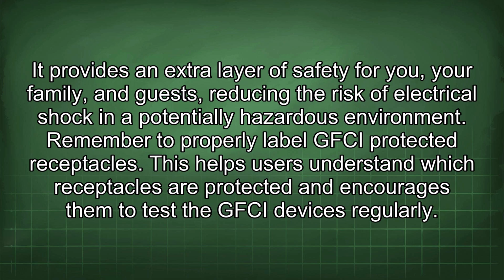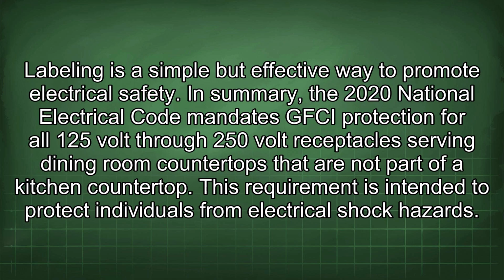a potentially hazardous environment. Remember to properly label GFCI protected receptacles. This helps users understand which receptacles are protected and encourages them to test the GFCI devices regularly. Labeling is a simple but effective way to promote electrical safety. In summary, the 2020 National Electrical Code mandates GFCI protection for all 125V through 250V receptacles serving dining room countertops that are not part of a kitchen countertop.